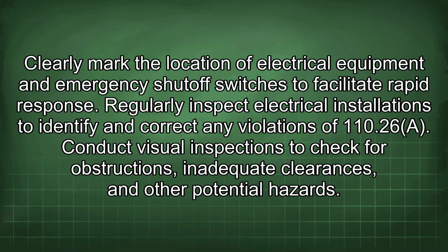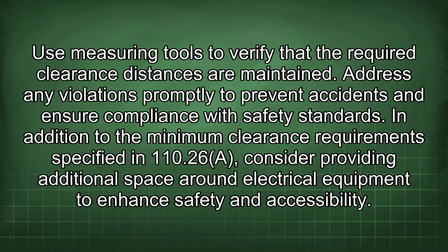Regularly inspect electrical installations to identify and correct any violations of 110.26(A). Conduct visual inspections to check for obstructions, inadequate clearances, and other potential hazards. Use measuring tools to verify that the required clearance distances are maintained. Address any violations promptly to prevent accidents and ensure compliance with safety standards.